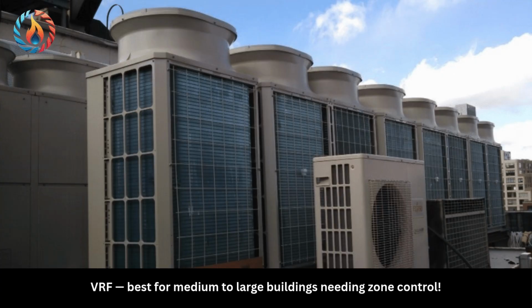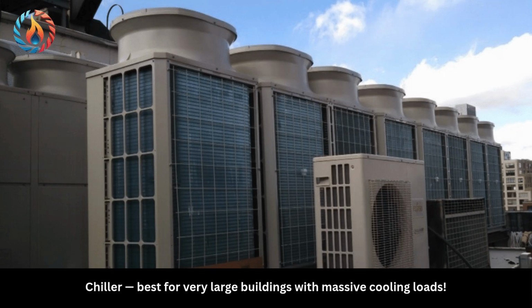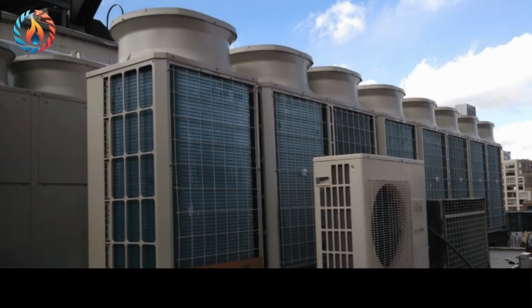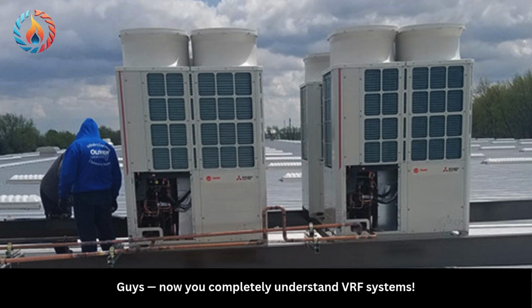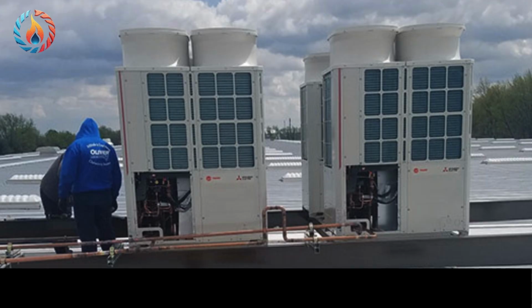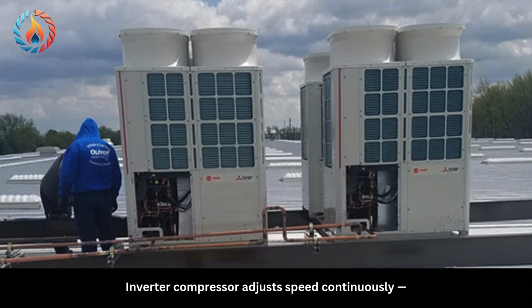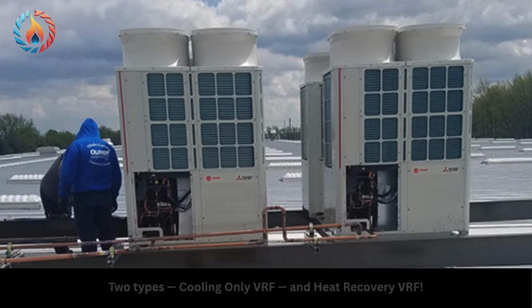VRF, best for medium to large buildings needing zone control. Chiller, best for very large buildings with massive cooling loads. Guys, now you completely understand VRF systems. VRF, variable refrigerant flow, one outdoor unit, multiple indoor units. Refrigerant flows to each zone as needed. Inverter compressor adjusts speed continuously. Each zone controlled independently. Two types, cooling only VRF and heat recovery VRF.